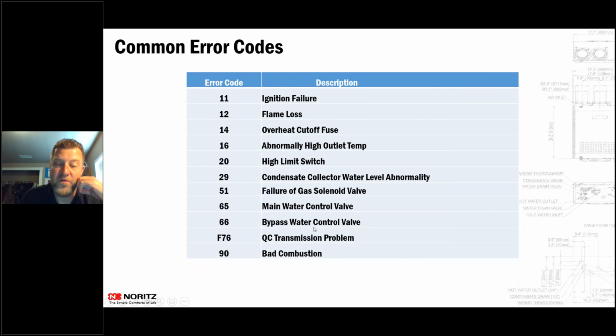66 is the bypass water control gone bad. One error code that's not on here that we see a ton of is 73. A 73 is a circuit board abnormality.